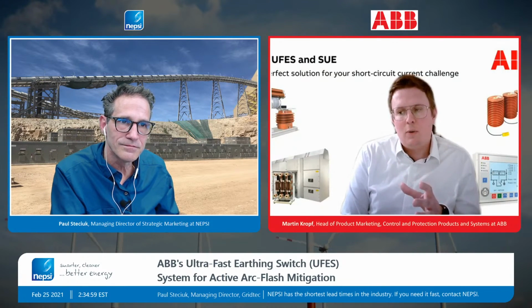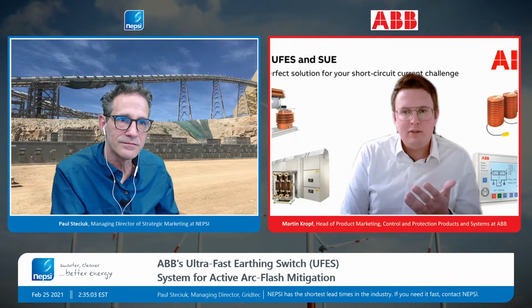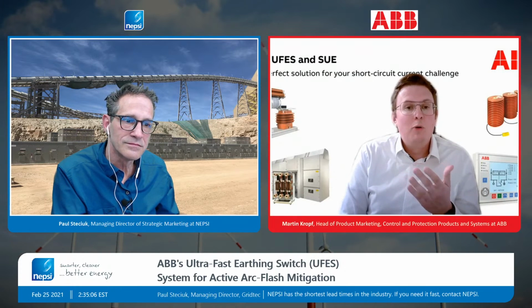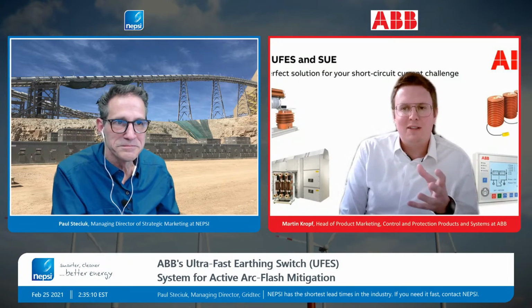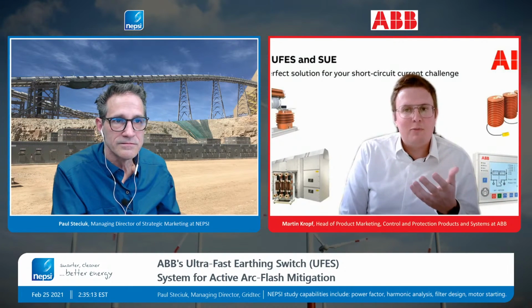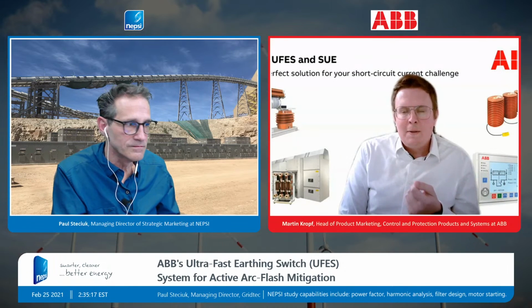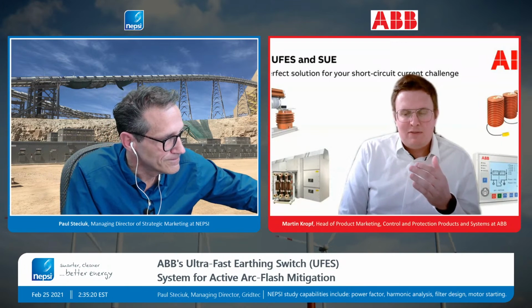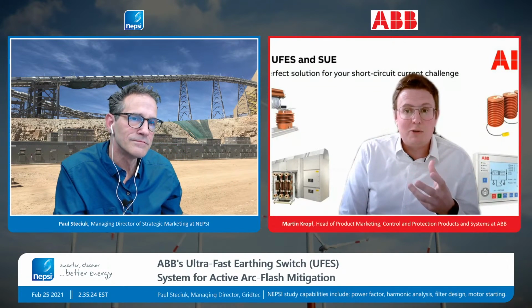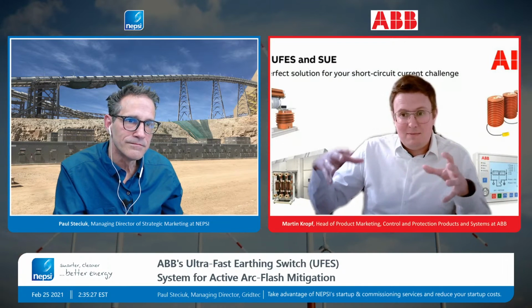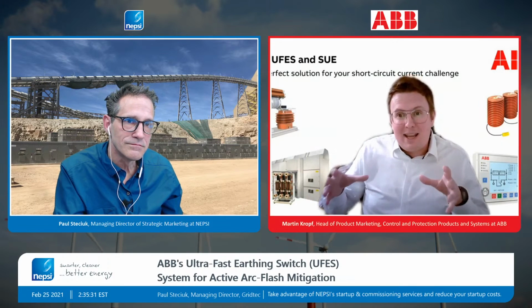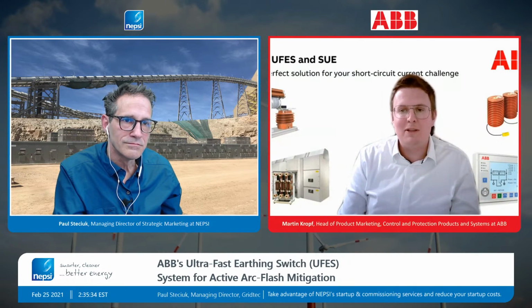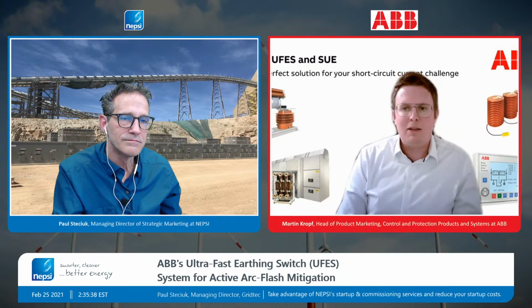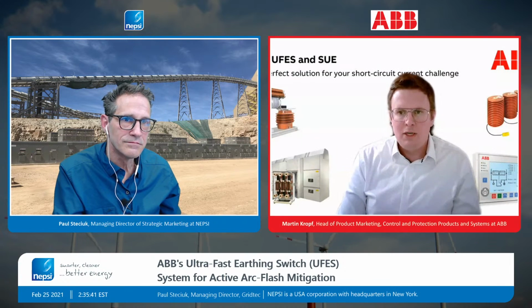It depends in these situations always who is doing it. We from ABB can do it. Sometimes, if it's your own manufacturer, for instance like you, Paul, it's not a switchboard, but it's your application in a capacitor bank, you can as a partner buy the loose component and install it for sure. We have different solutions. We have a truck-mounted version, for instance, if it's a very new switchboard and you don't want to open the switchgear and add something, so you can rack in, rack out, and have a very clear interface, and maybe the owner doesn't want to lose the warranty. But if it's older equipment, we have retrofit solutions, and as I said, partners install it loose in their own device to offer a differentiation as well.